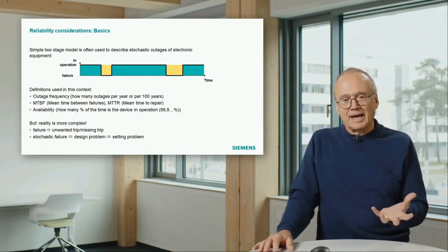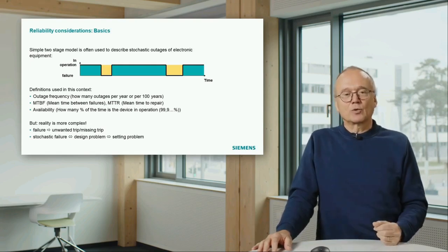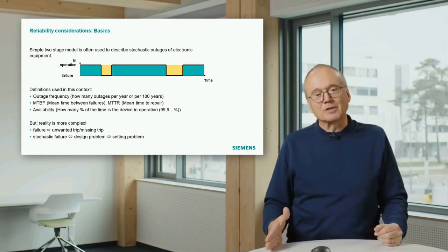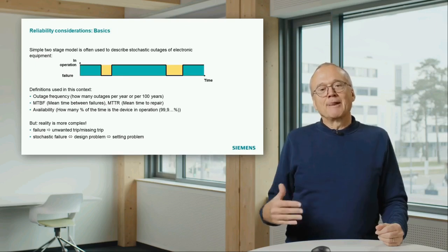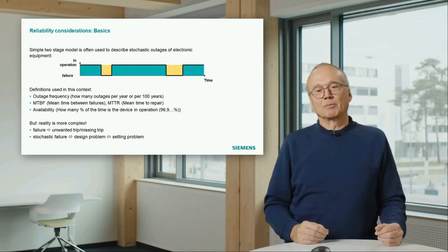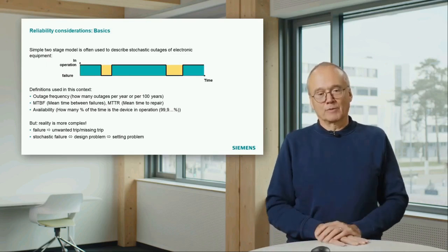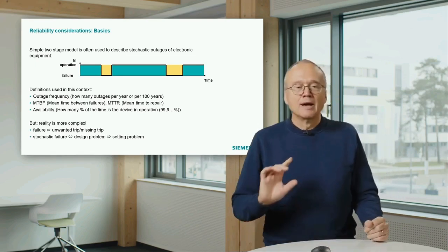It's always there and it shows up in a dedicated situation. Or if you have a setting problem, this problem is always there, but it becomes only visible if you have a fault at a location where this setting problem results in a wrong reaction. And this has to be taken into account.